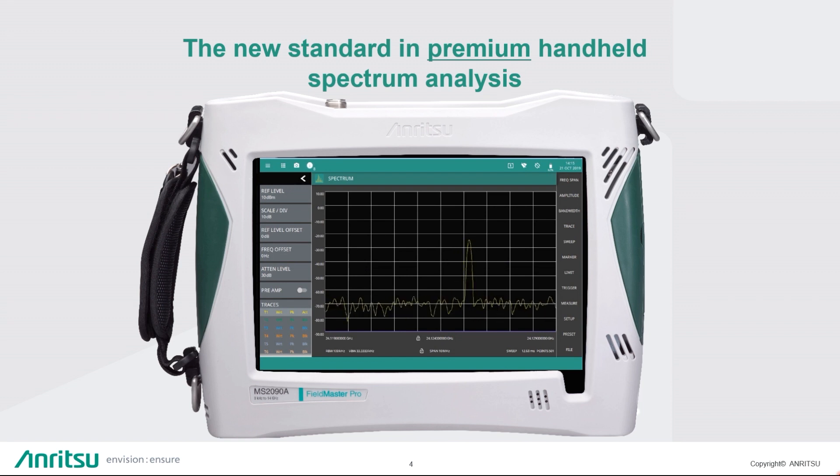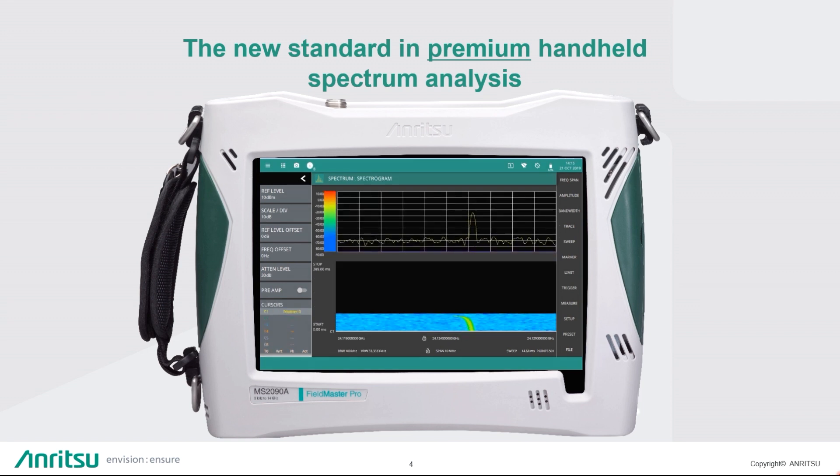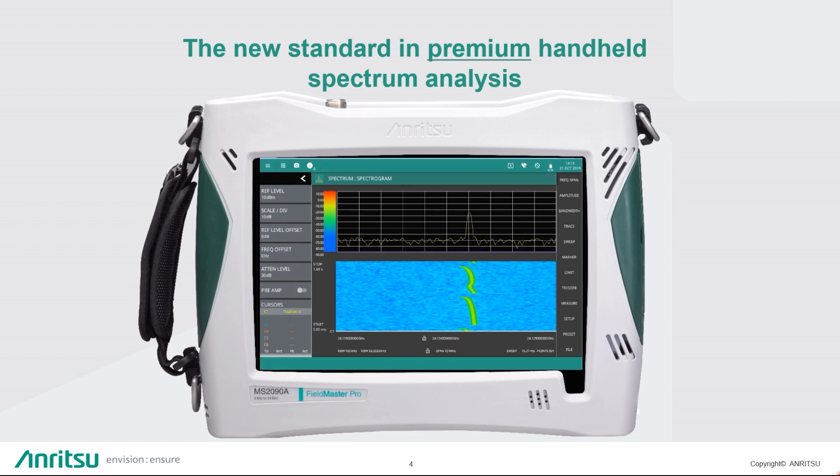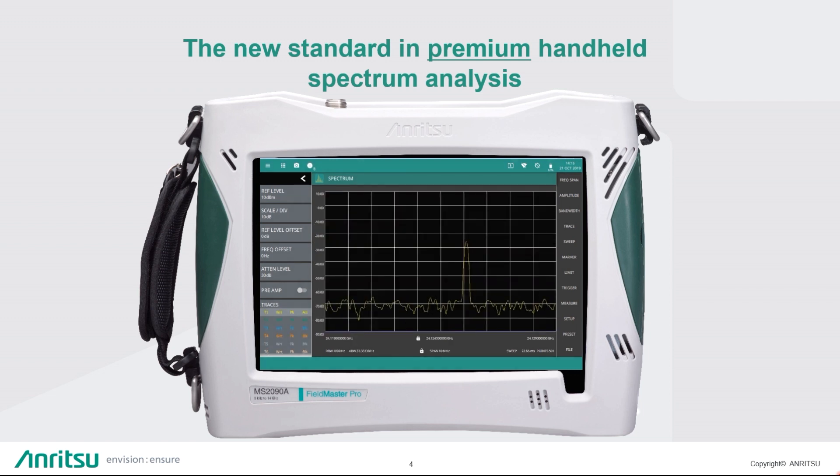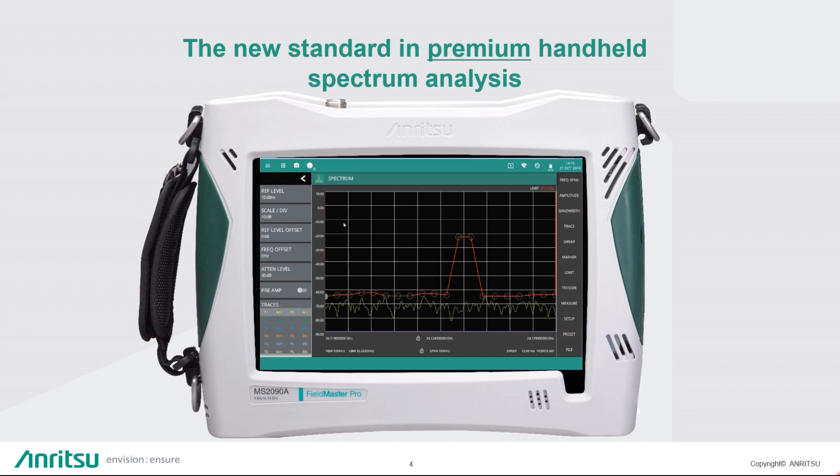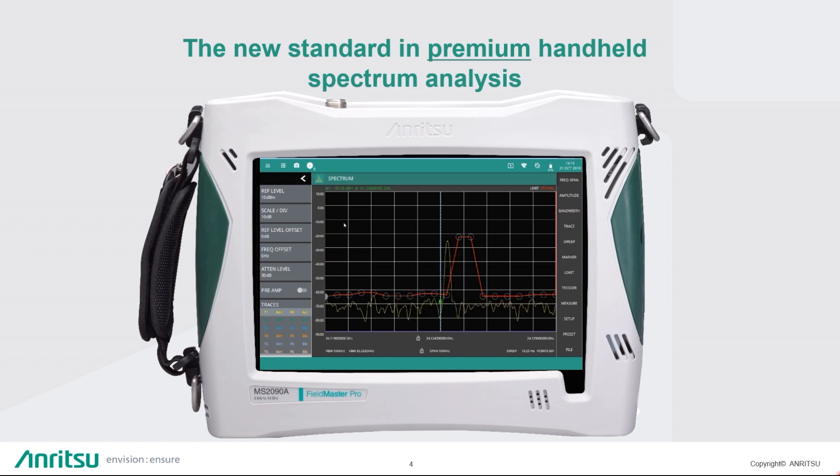The measurements can easily be made by using the main instrument functions like frequency, span, amplitude, and bandwidth. Also, upper and lower multi-segmented limit lines are available to create quick, simple pass-fail measurements. A full range of marker capabilities such as peak, center, and delta functions are provided for faster, more comprehensive analysis of displayed signal.